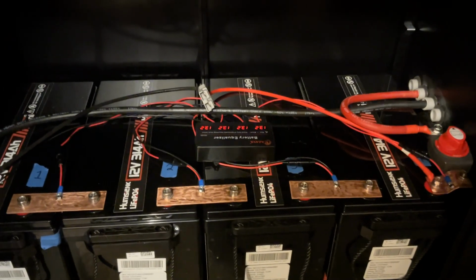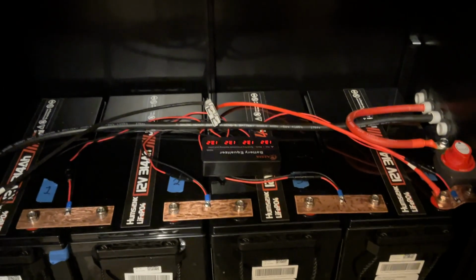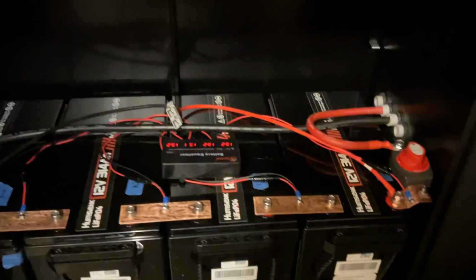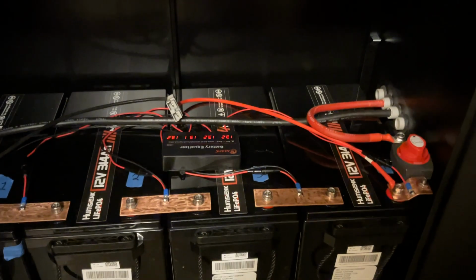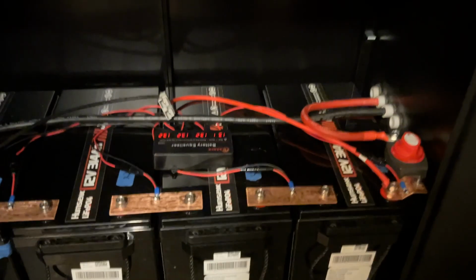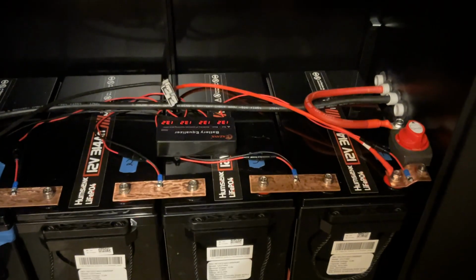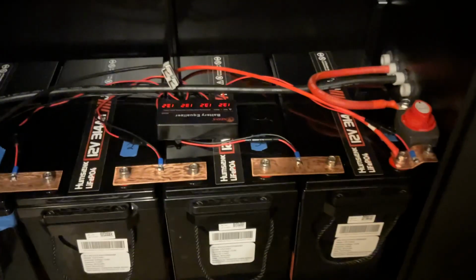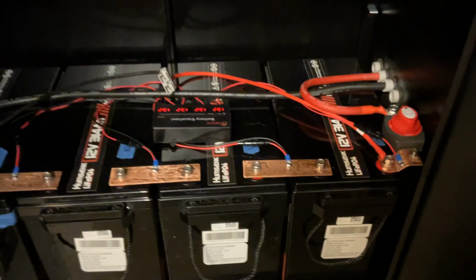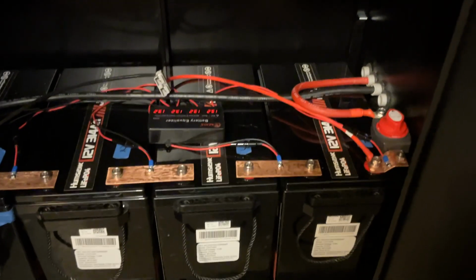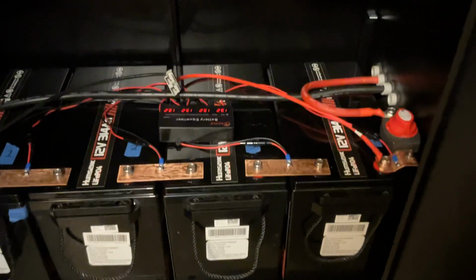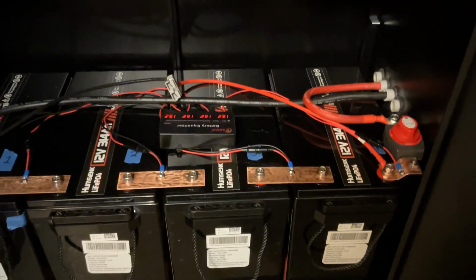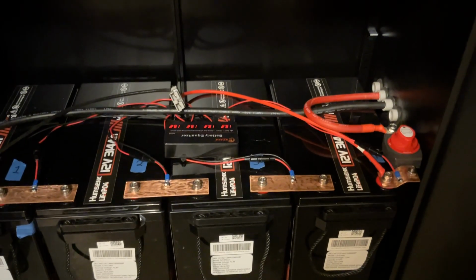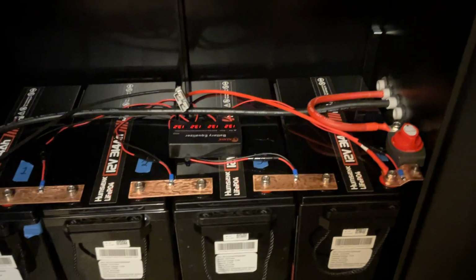When I noticed that battery 4's voltage was showing low on the battery balancer, I did some testing with my Fluke meter and confirmed the output voltage in that battery was low, and that's when I noticed the FETs were turned off. I was curious why my inverter was still turning on fine and would run with no load or a very low load, less than 2 amps DC from the battery bank. It would carry the lights in my garage.